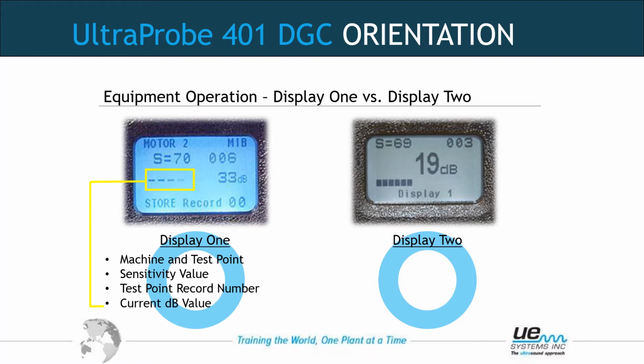The decibel or flashing arrow appears in the box here. This arrow is flashing to the right. The arrowhead is not formed yet, as when the picture was taken, it was in the middle of flashing. The arrowhead would be sitting here and flashing to the right. This indicates the sensitivity is not high enough and the unit cannot get enough input to form an actual digital decibel. If it's pointing to the left as it flashes, that means turn the sensitivity down, as it is too much input to form a digital decibel. Once a numeric value appears, the decibel, we have the instrument set correctly.